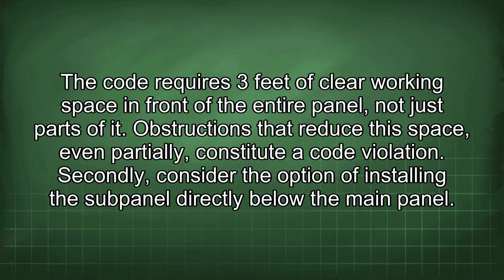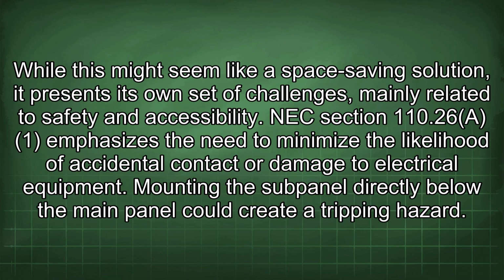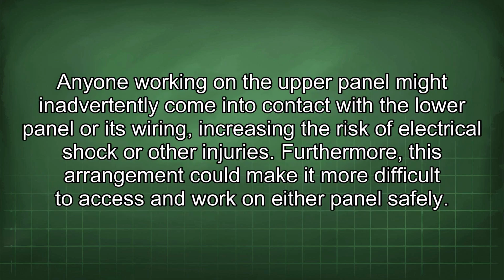Secondly, consider the option of installing the subpanel directly below the main panel. While this might seem like a space-saving solution, it presents its own set of challenges, mainly related to safety and accessibility. NEC Section 110.26(A) emphasizes the need to minimize the likelihood of accidental contact or damage to electrical equipment. Mounting the subpanel directly below the main panel could create a tripping hazard. Anyone working on the upper panel might inadvertently come into contact with the lower panel or its wiring, increasing the risk of electrical shock or other injuries.